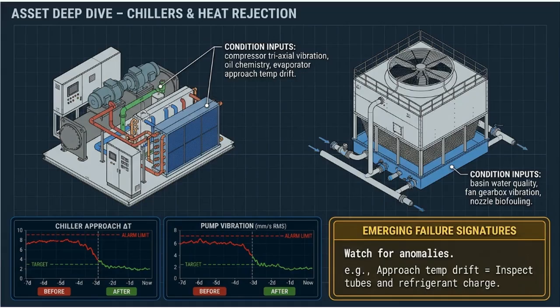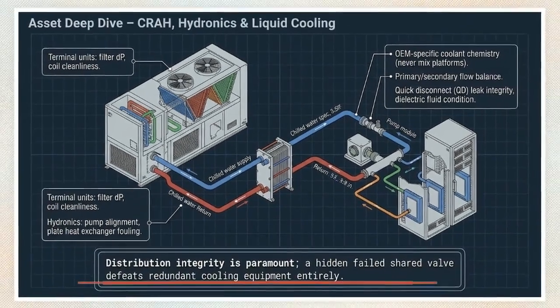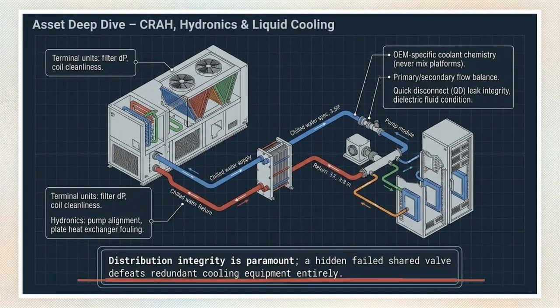This deep dive into chillers and heat rejection shows the specific condition inputs operators track. The charts highlight emerging failure signatures, like spikes in compressor triaxial vibration or subtle downward drifts in evaporator approach temperatures. Isolated maintenance provides a window to hunt for hidden threats across the distribution network. A single failed shared valve can silently bypass coolant and entirely defeat the redundant computer room air handlers and direct-to-chip cooling loops.